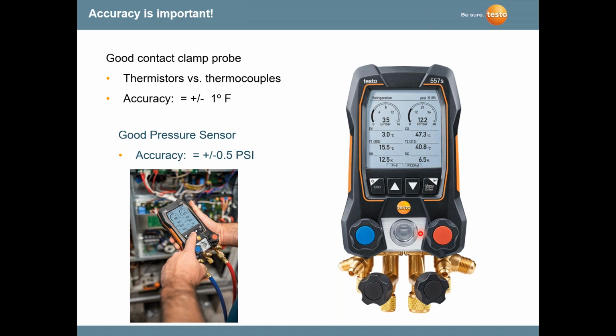But like I said, I keep saying accuracy is important. Just to give you an idea, plus or minus 1 degree Fahrenheit is the accuracy of the thermistors. And this is a thermistor, not a thermocouple. Thermocouple is much higher than that. The pressure sensors are 0.5, that's a half of a PSI. So you're going to be reading PSI in 25.4, 25.6. So you'll be reading that 1/10 of a PSI on these gauges. Same thing with the degrees Fahrenheit or the degrees Celsius. You're reading down to a 0.1, 0.2 degree Fahrenheit or Celsius.